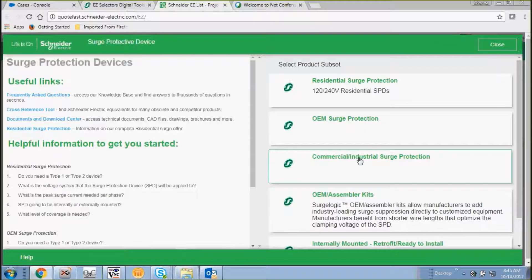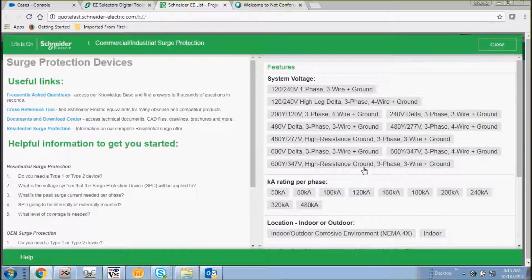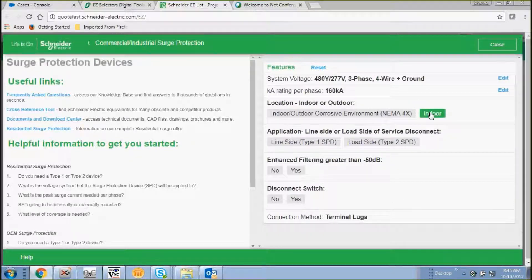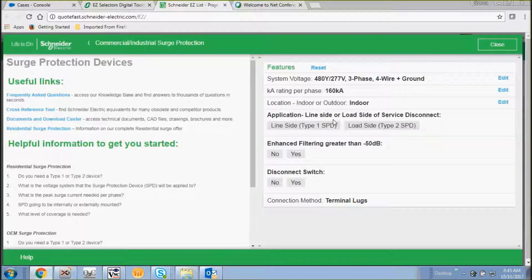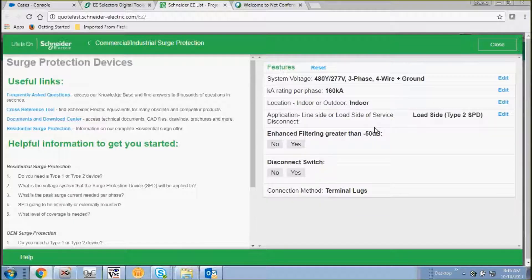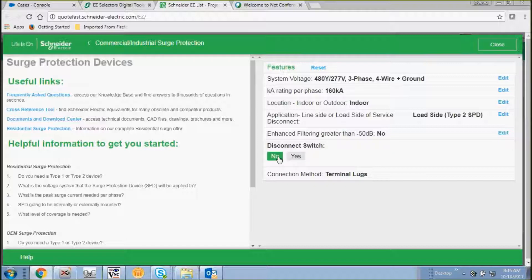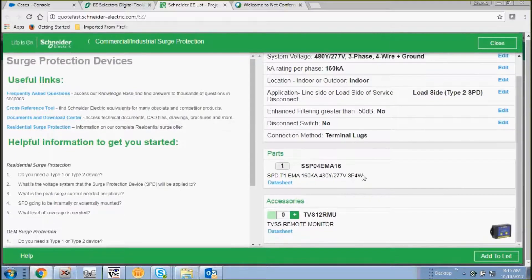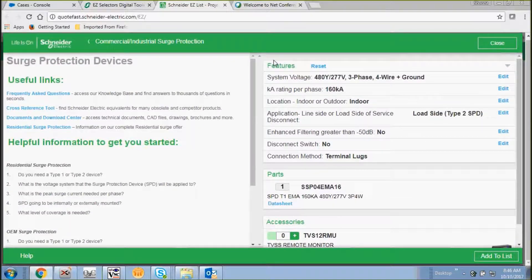Now we're going to do commercial industrial surge protection. As you can see, the options have increased. Let's select 480Y/277V and also select our peak surge current rating, and we're going to mount this indoors. Here you have an opportunity to choose from load side and line side protection — we're going to choose load side protection. We don't need any filtering, so we'll select no. We don't need a disconnect switch, so we'll select no there as well. As you can see, we've generated a part number. This part number is one that can be mounted externally. You also have an option to get a remote indicator.